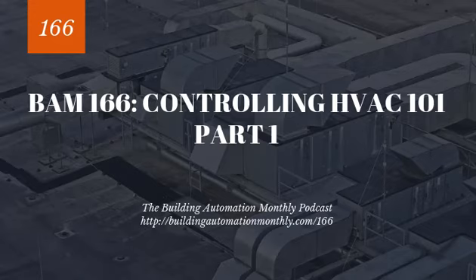And there's all sorts of ways you can avoid this. You can mess around with the volume going into the spaces and the volume going out to make sure that those become more positive than the actual hallway. And this is what a balancer should be doing on the job site when a job is first commissioned, or when a job is actually being retrofit.